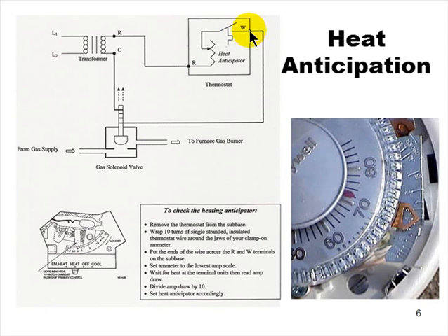You're going to wait until the heat comes up in the building. If it's baseboard, wait till you hear the baseboard start to expand and you feel heat in the registers. If it's hot air, wait till the fan comes on and starts blowing hot air. Because you don't want to see the instantaneous reading. You want to know how much amperage this is going to generate while it's running. Because that's when it comes into play, and that's what's going to cause this to shut off.